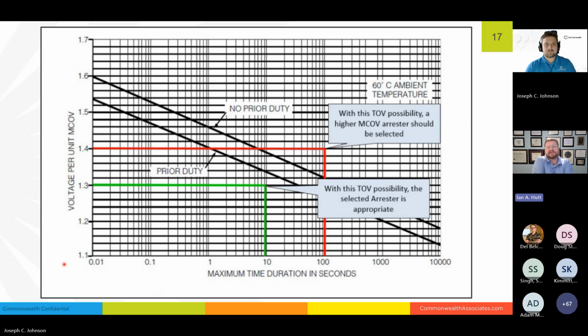So we can see a couple of looks here. If you look at this graph, you can notice that it's a log graph with time as your x-axis and voltage as your y-axis. But note that voltage isn't per unit of nominal voltage; it's your MCOV per unit. So note that your nominal voltage will likely be slightly less, just like we discussed in our question. Your MCOV rating needs to be above your nominal rating on a line to ground value. And how big that margin is depends on your application, your margins, and some other things that might come out of your insulation coordination studies. But you'll note that for shorter duration times, you can have a higher voltage allowed with these TOV events.